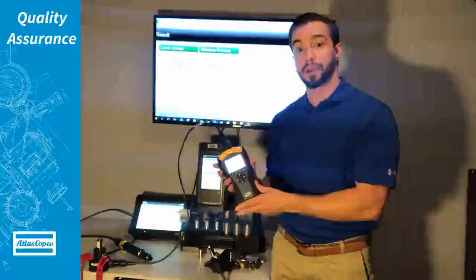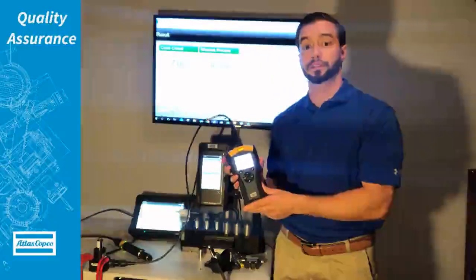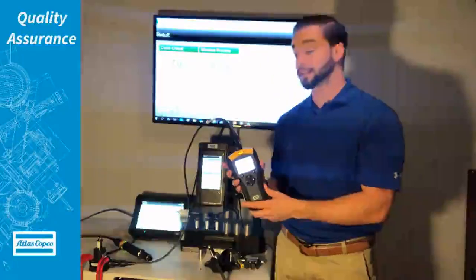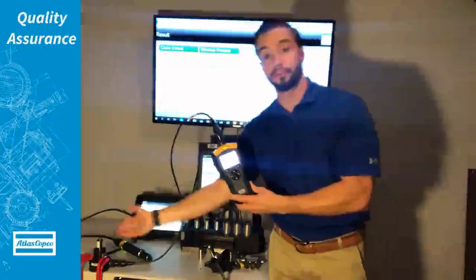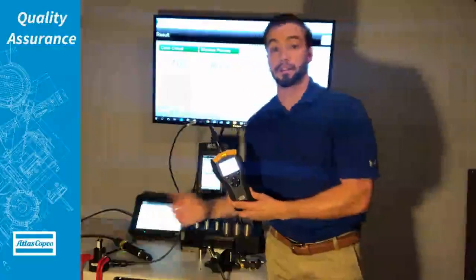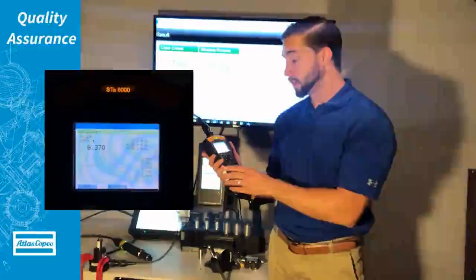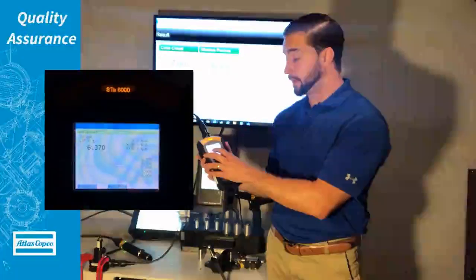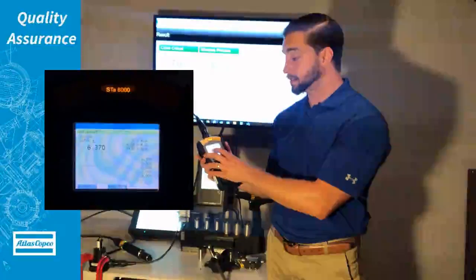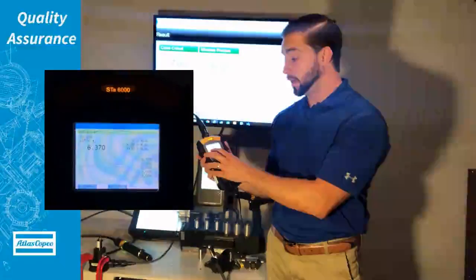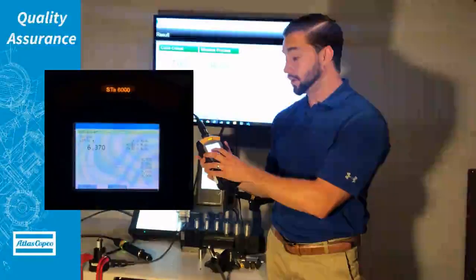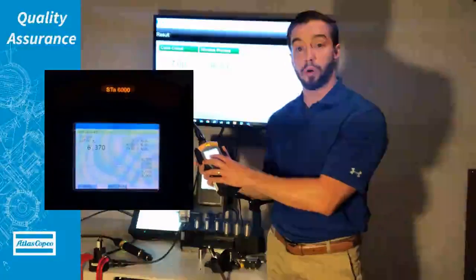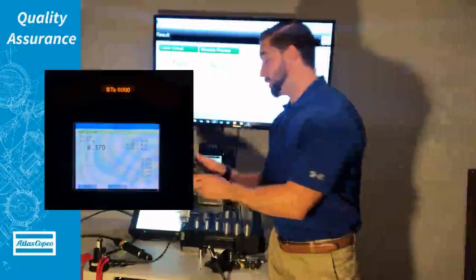So we're comparing the two different transducer readings, the one from the tool and the one from the SRTTB here. We have a torque result on the STA 6000 of just under 6.4 inch pounds.